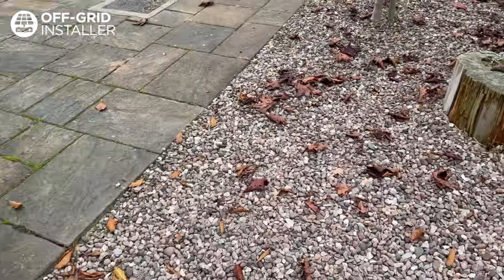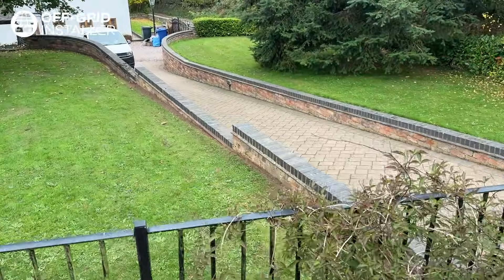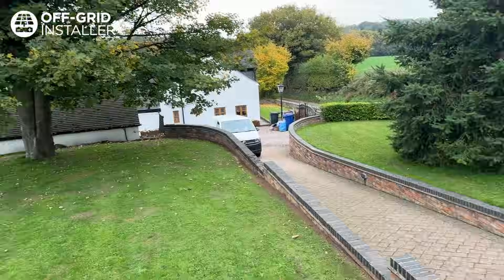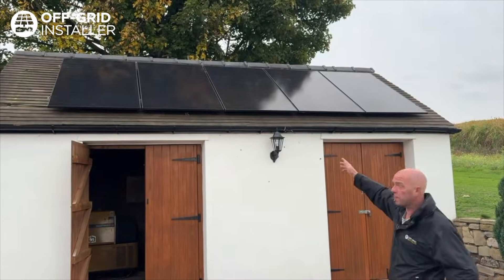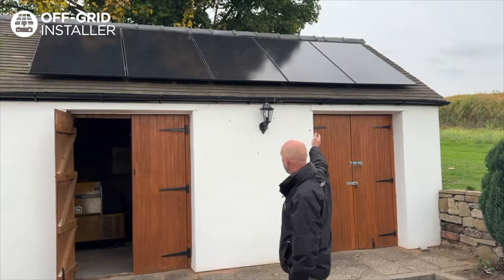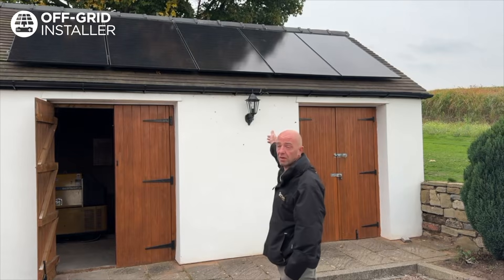The solar cables come up off the roof into two DC isolators, then go into an armored cable which runs down along the edge of that wall. You can see we've dug up there and all the way into the plant room. We've got five panels up on the roof here — each panel is 505 watts, giving a total of 2,525 watts.